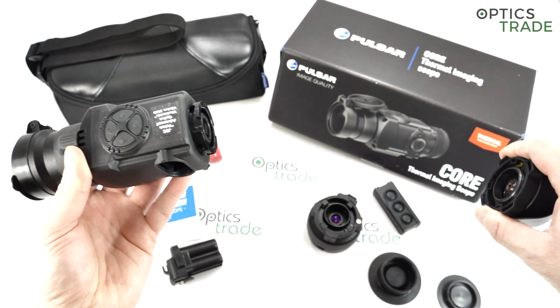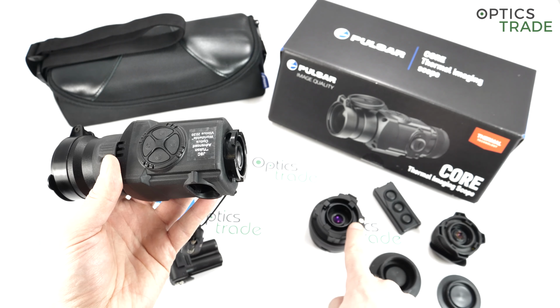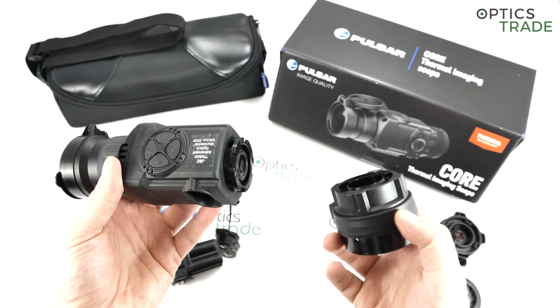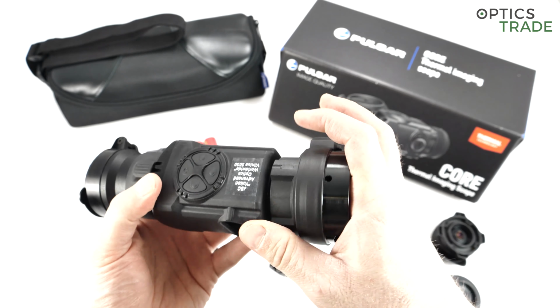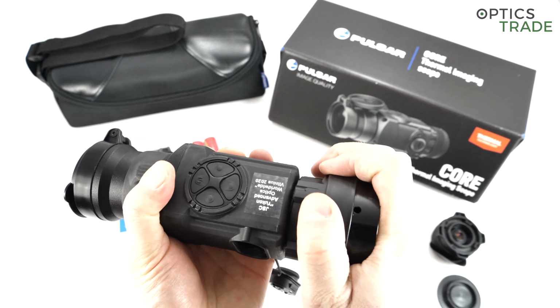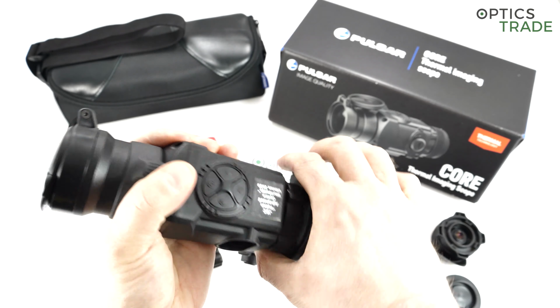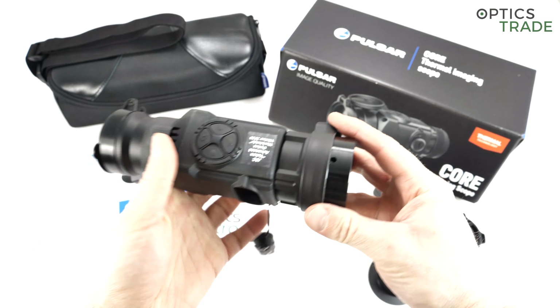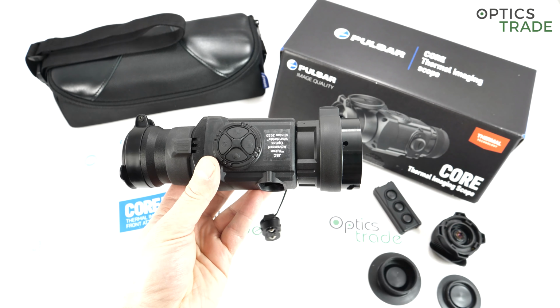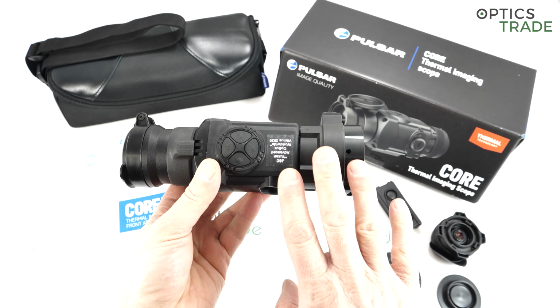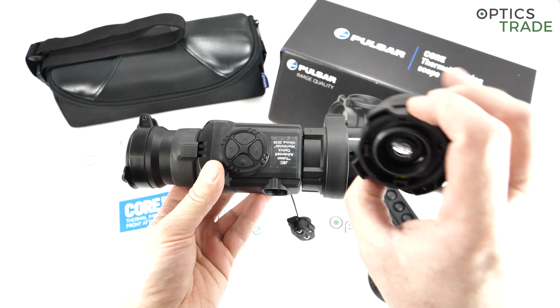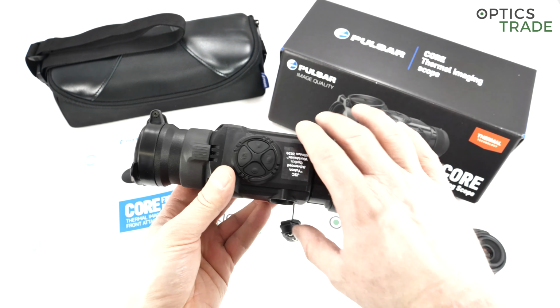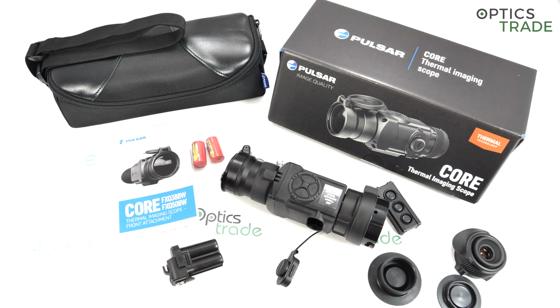What's true, and what you need to be careful about, is this small magnet on the bayonet. You can do the zeroing of the device, if needed, only when this middle part is on the device. You're not able to zero it with the monocular attached. This is a protection so that you're only able to zero the device when it's mounted on a daytime scope.